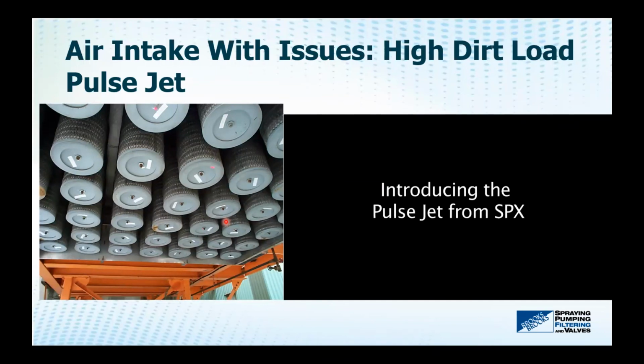So it's a continuous operation whereby the customer, in a case of a high contaminant or high dirt area, can continue to operate for long periods of time without having to do maintenance on filters. And these would typically be installed in locations where they want to minimize human intervention, so they're self-monitoring, self-cleaning, and typically the duration of these elements easily exceeds a year. Sometimes I've been told that they exceed 3 to 5 years, but it's always dependent on the dirt levels.